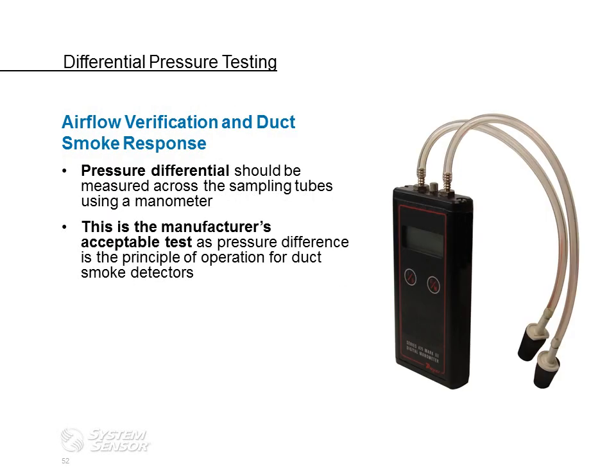Now, we've talked about pressure differential and the principle of operation of a duct detector. This is something that should be done on every duct detector that's installed or in the field. Airflow verification and duct smoke response. Pressure differential should be measured across the sampling tubes using a manometer. This is a manufacturer's acceptable test, as pressure difference is the principle of operation for duct smoke detectors. If we don't have that pressure differential, that means we don't have airflow, and if we don't have airflow, the duct detector is not going to function correctly.